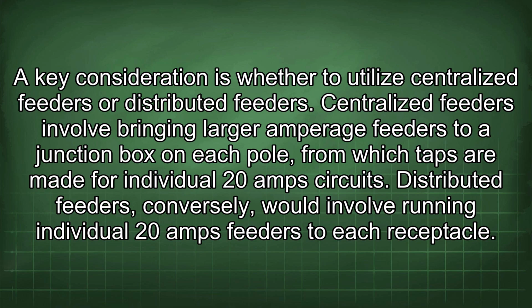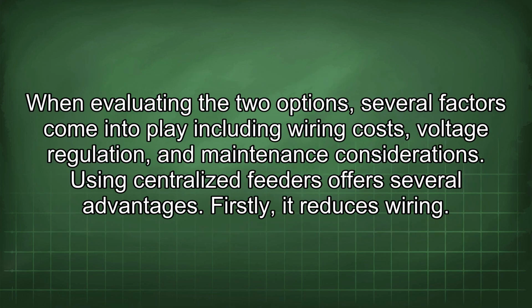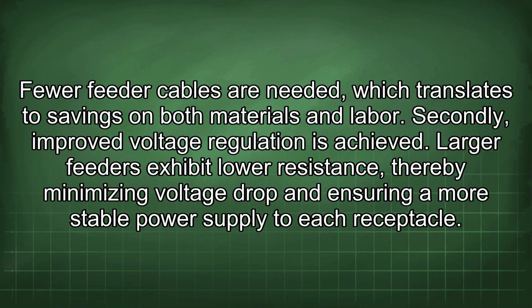Centralized feeders involve bringing larger amperage feeders to a junction box on each pole, from which taps are made for individual 20 amp circuits. Distributed feeders, conversely, would involve running individual 20 amp feeders to each receptacle. When evaluating the two options, several factors come into play, including wiring costs, voltage regulation, and maintenance considerations. Using centralized feeders offers several advantages. Firstly, it reduces wiring. Fewer feeder cables are needed, which translates to savings on both materials and labor.